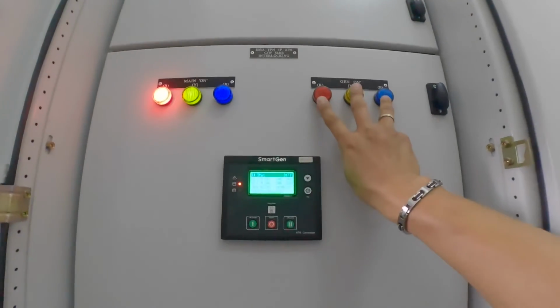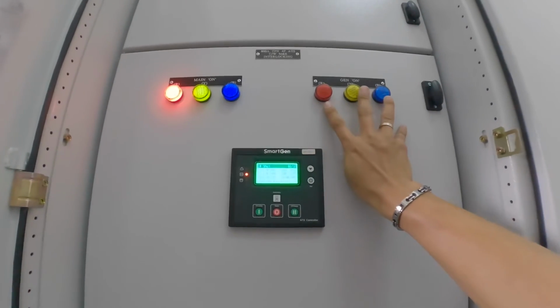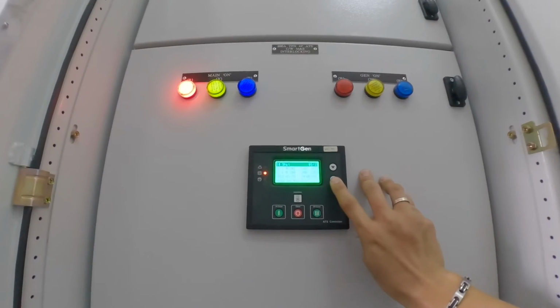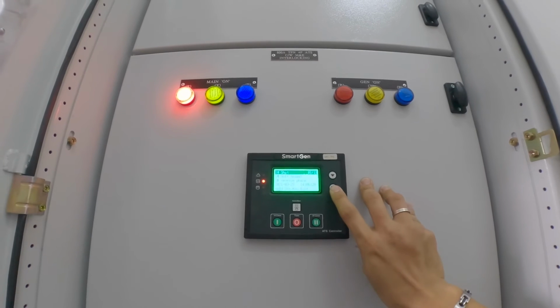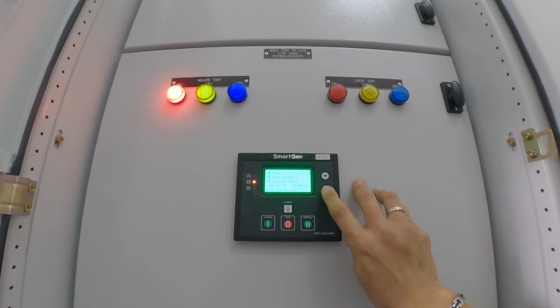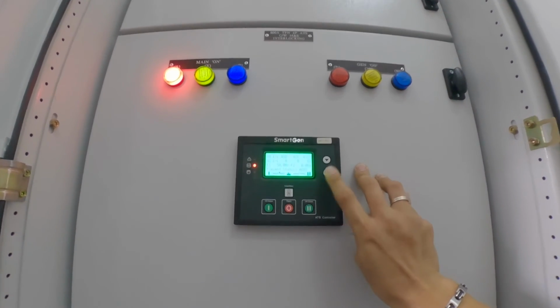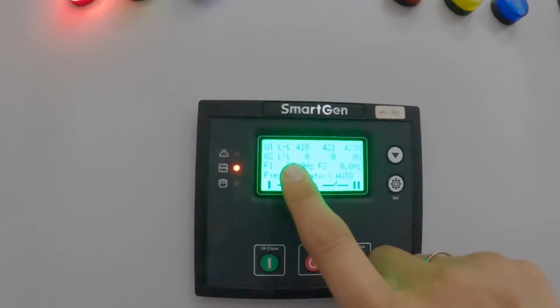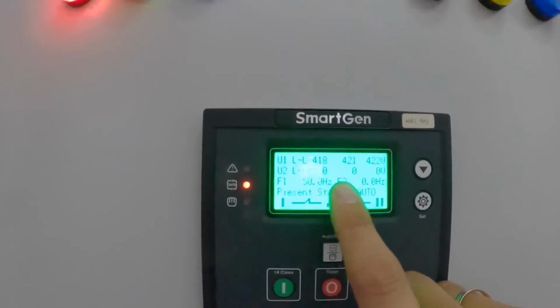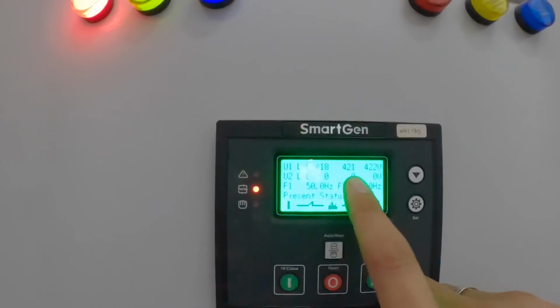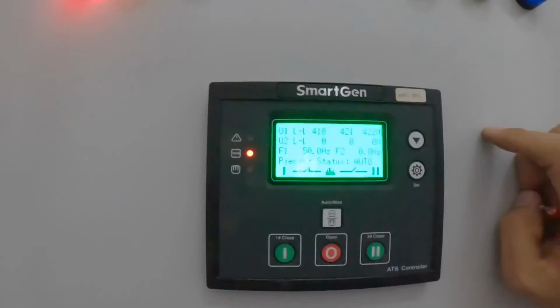Here we have the genset already stopped. As we exit it, we can see the genset voltage signal is already 0, so only the main supply reading remains. The testing is over and everything is in good condition.